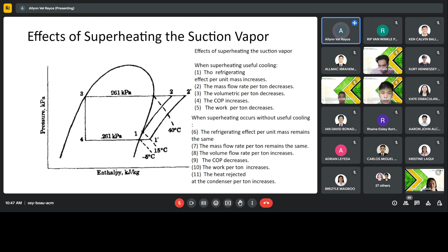With the use of useful cooling, we use a heat exchanger. But like this one, there are processes that superheat without the use of a heat exchanger. Are we clear on that? In this case, the process is still 1, 2, 3, 4, but with the heat exchanger, we have superheating and subcooling, so we end up with 6 state points.